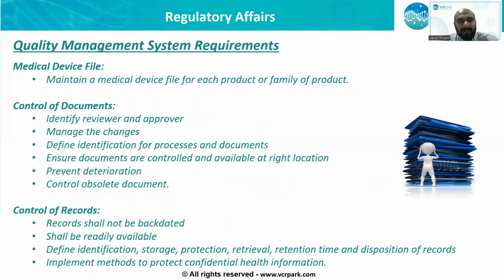From a quality management system general requirement perspective, there are 3 key requirements that we need to fulfill. One is maintaining a medical device file. For every product that your organization might be developing or designing, we are expected to maintain a medical device file. Imagine it to be a document, or a folder, which has all the relevant information for that particular device, which includes right from the intended use of the device, the labeling and packing of the device, the design specifications of the device, any installation or servicing that is needed for the device, things like that. So there are a set of requirements that need to be captured in the medical device file, and for every device, the medical device file needs to be maintained.